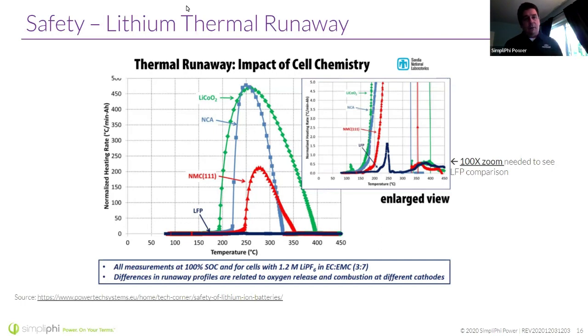For example, with the green curve, it starts very early, goes very high, and ends very late. Similarly, the NMC curve in red is pretty significant, not as high as green or blue, but we don't even see the LFP cell on this first scale. We actually have to zoom in 100 times to see the LFP curve, which starts later and ends earlier—not as dramatic an off-gassing event, resulting in less energy from that boiled-off electrolyte, potentially producing a smaller thermal runaway event.